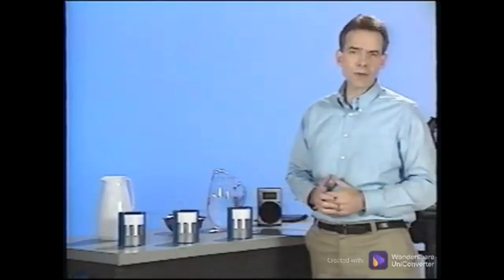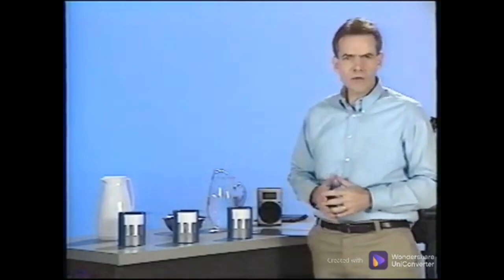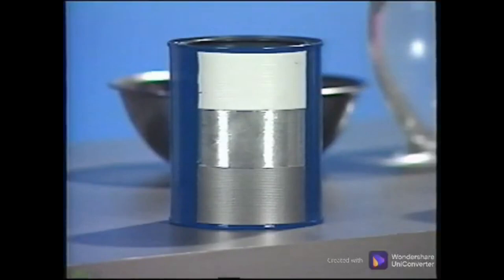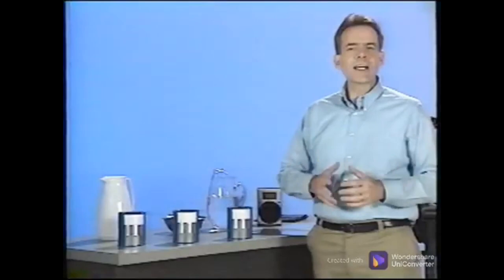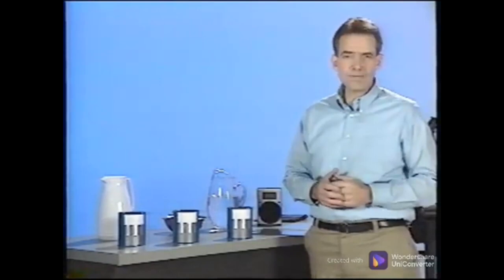What causes this? Are the silver tapes actually a different temperature? The tapes on a can really are the same temperature, but let's look at them more closely to determine the cause of the apparent temperature difference. Notice that the white and gray tapes appear the same color or temperature, and they both have the same textured surface. However, the silver tape has a smooth or reflective surface. This reflective surface is actually reflecting the ambient temperature of the room, or background temperature, and therefore does not radiate or emit the true temperature.